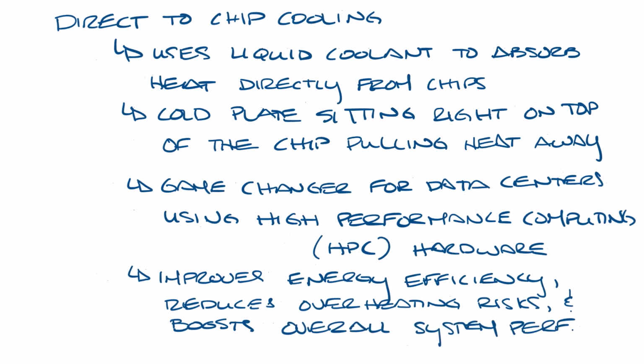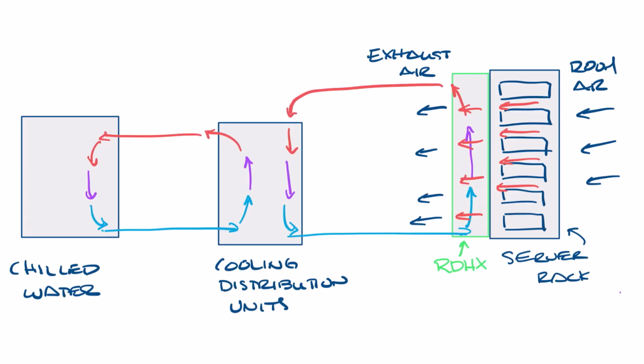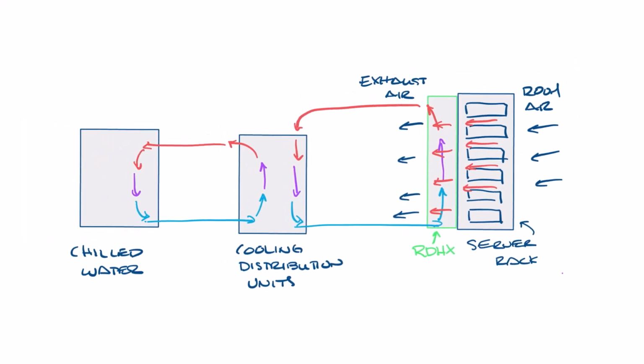Let's move this over to draw the system. Similar to the rear door heat exchangers that I talked about in the last video, you'll have a cold water loop. So let's just pull the drawing from that last video. Somewhere on site, you'll have a chiller and a chilled water loop that sends water to coolant distribution units, CDUs, that use liquid-to-liquid heat transfer to cool the liquid loop going to the cold plates on the chips.